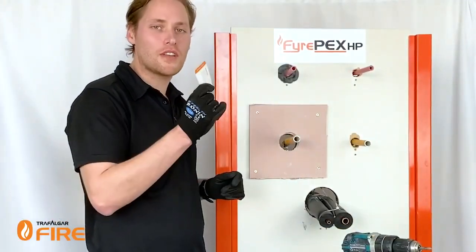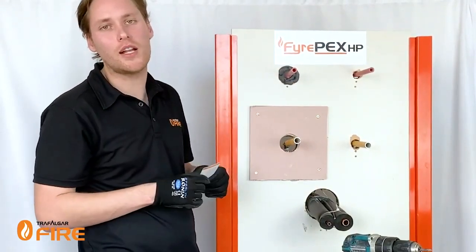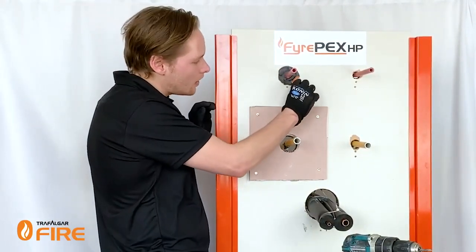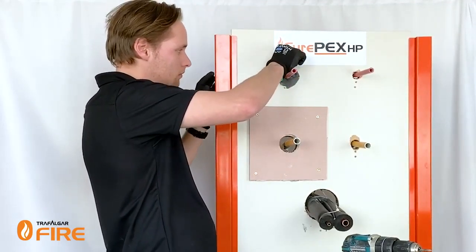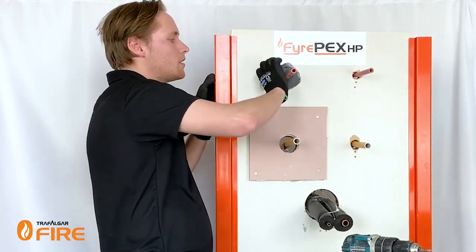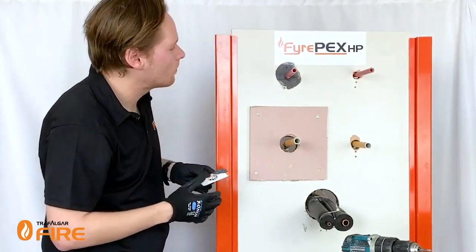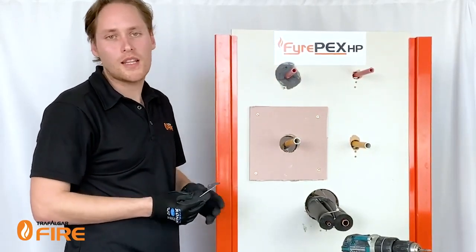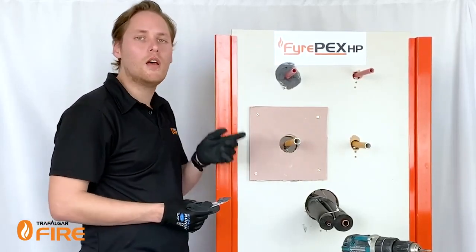I'm just going to tool this off with a bit of cardboard to make sure that we're pushing the sealant into the depth of the wall and giving it a nice clean finish — just take the cardboard and scrape it around like this. You don't have to use a fillet with our FyrePEX system; it just needs to finish flush with the wall. And there you go — that's how we treat a two-hour plasterboard wall with two layers of plasterboard on both sides.